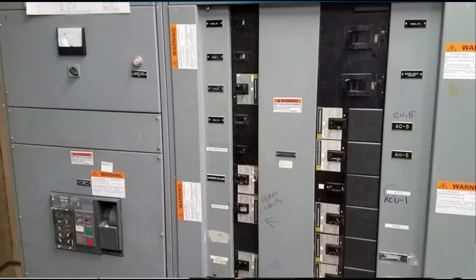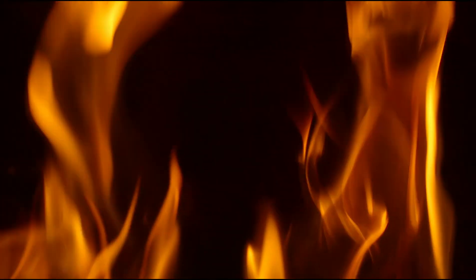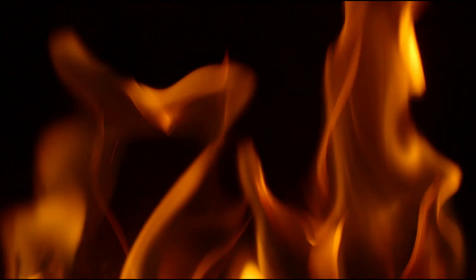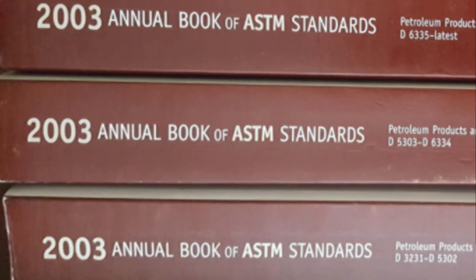Part of this is ensuring that arc flash hazard equipment labels are in place and that the employee has the information necessary to select the appropriate PPE based on the label. Incident energy is defined as the amount of thermal energy impressed upon a surface at a certain distance from the source, generated during an electrical arc event. It is typically expressed in calories per centimeter squared in the United States, and in joules per centimeter squared in many other parts of the world. Incident energy calculations are based on available thermal energy only and do not calculate the severity of other hazards. ASTM International, formerly known as the American Society for Testing and Materials, is an international standards organization that develops and publishes voluntary consensus technical standards for a wide range of materials, products, systems, and services.